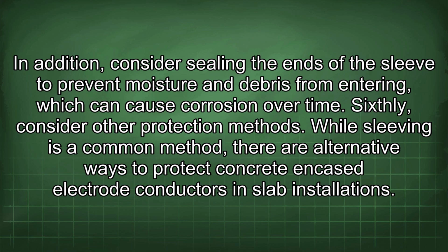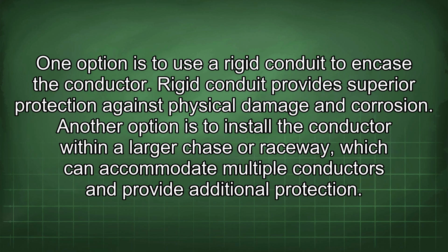Sixthly, consider other protection methods. While sleeving is a common method, there are alternative ways to protect concrete encased electrode conductors in slab installations. One option is to use a rigid conduit to encase the conductor. Rigid conduit provides superior protection against physical damage and corrosion. Another option is to install the conductor within a larger chase or raceway, which can accommodate multiple conductors and provide additional protection.